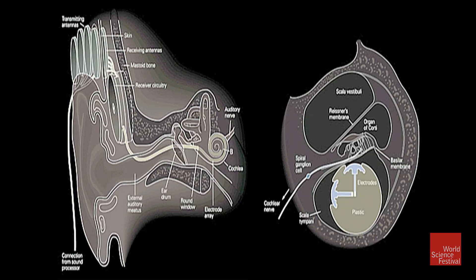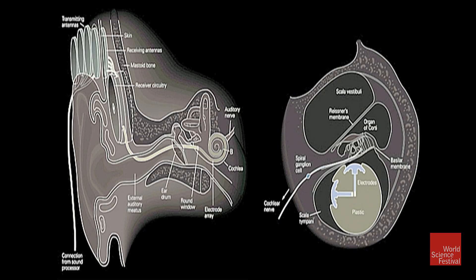This gives you some idea of how the implant or prosthesis works. Basically, there's an externally worn device that's sort of like a hearing aid. It picks up sound from the environment, breaks it down into different frequencies — the job that the hair cells normally do — and then sends that electrical information down a wire. You see at the left the externally worn device, then the wire that's tunneled surgically into the cochlea, and it ends in a series of electrodes that actually shock the cochlear nerve that sends information on into the brain.